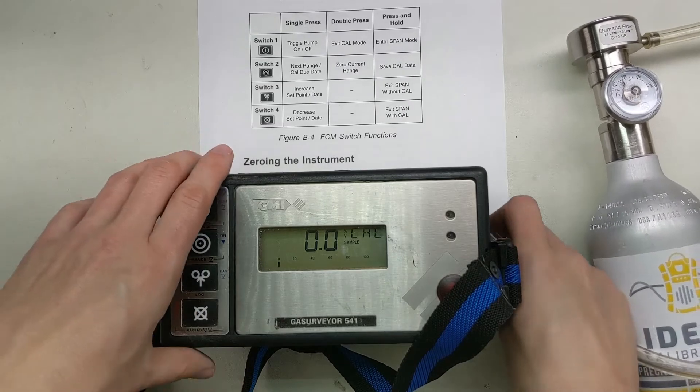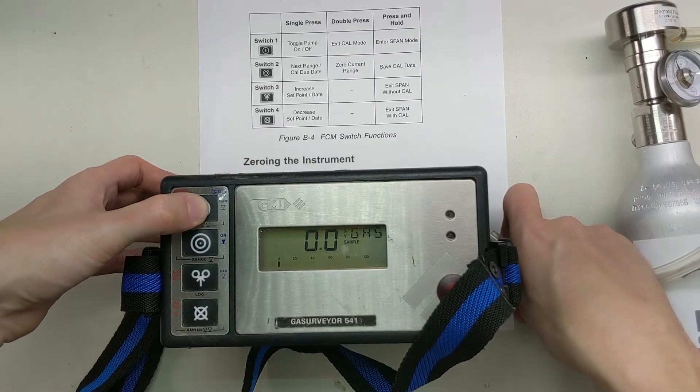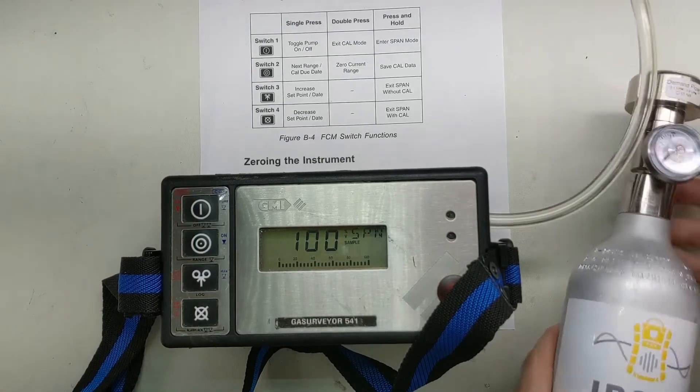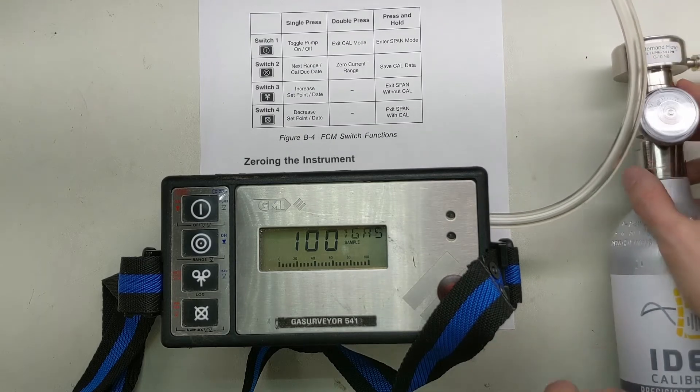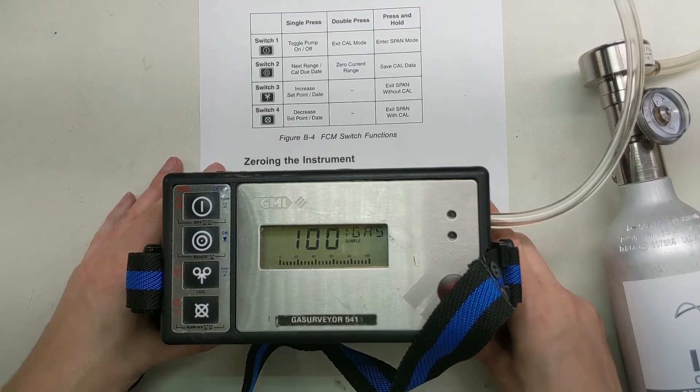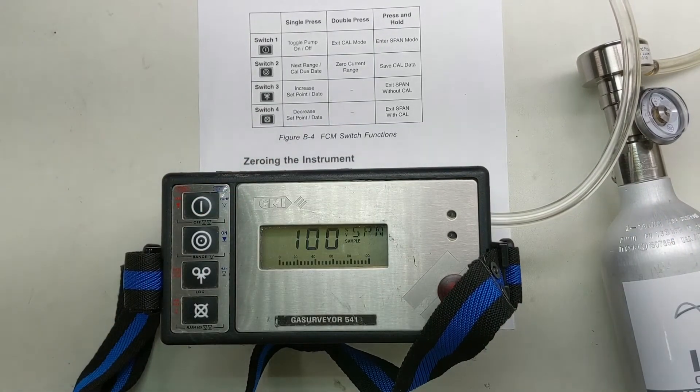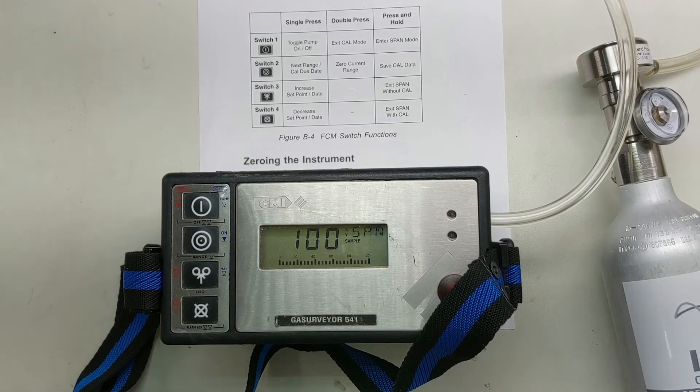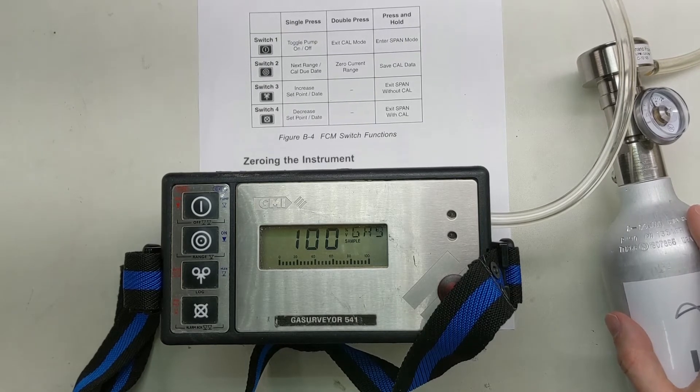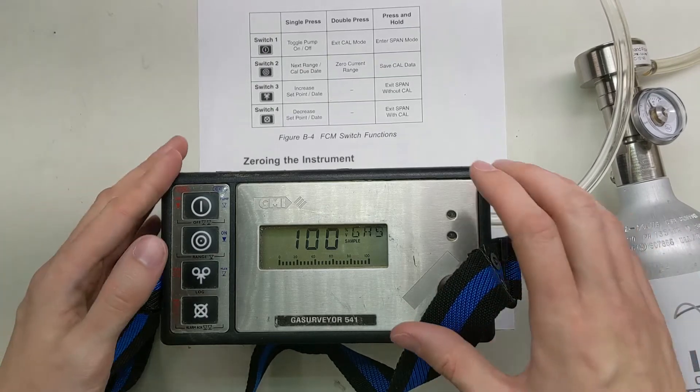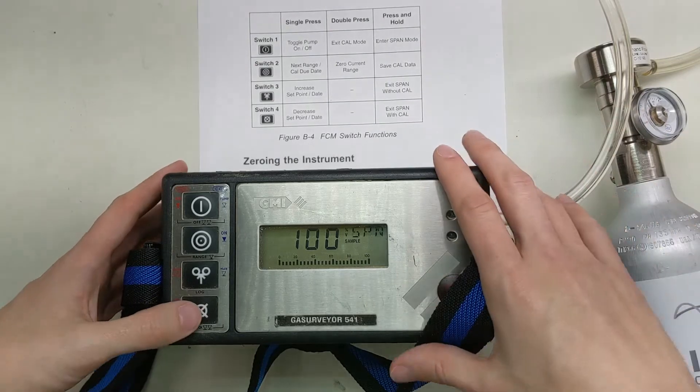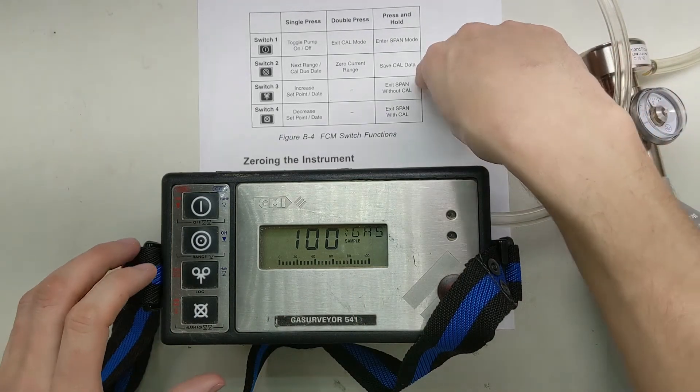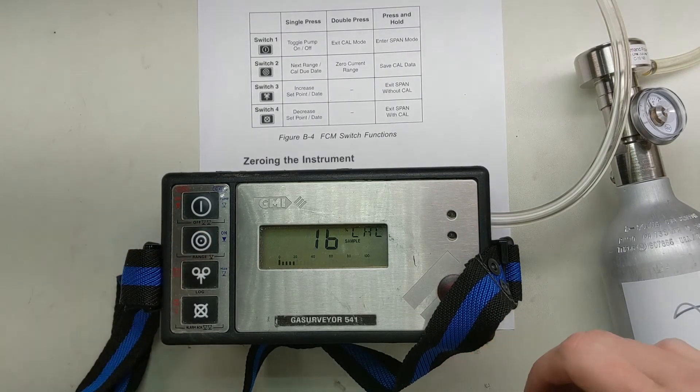Now we're going to go ahead and enter span mode. Press and hold the button here. Now it's looking for a 100 gas. I'm going to put this on here. This sensor is a little different than the LEL sensor. It's called a TCD, thermal conductivity detector. It reacts a little bit quicker. So we don't have to wait as long. What we're going to do, exit span with Cal. Now it's showing 99 and 100 for our reading. Perfect.